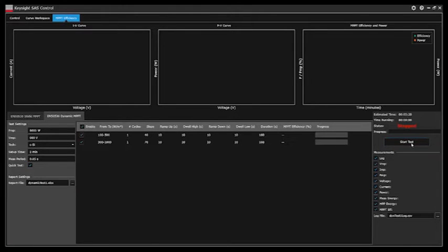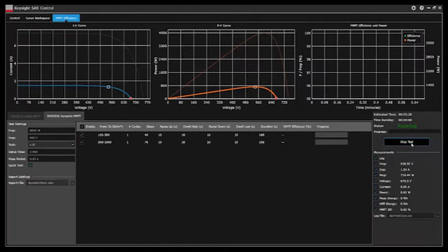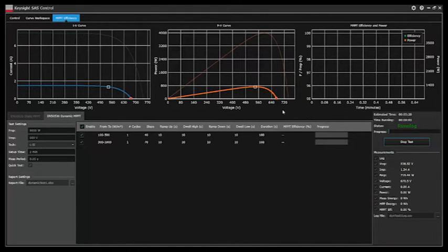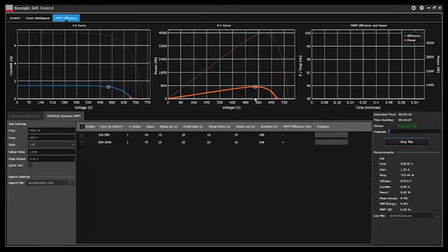We'll download the curves down to the instrument. We'll turn on the output and we'll wait for the inverter to start tracking the MPPT. Now this will take a couple minutes so in the interest of time we'll come back here in just a minute.